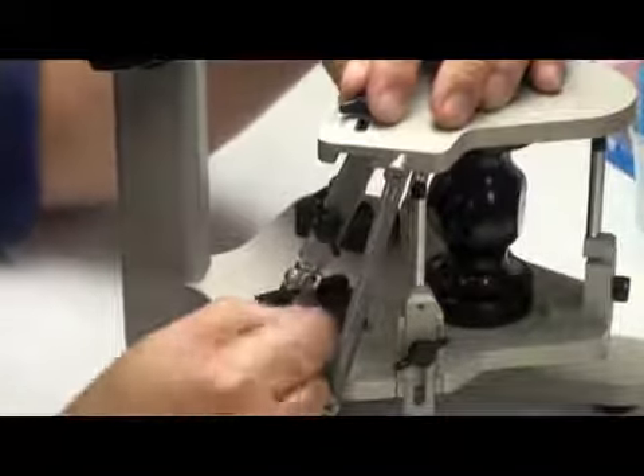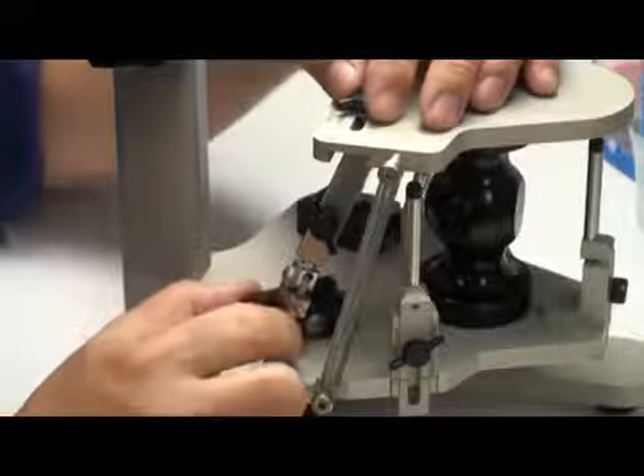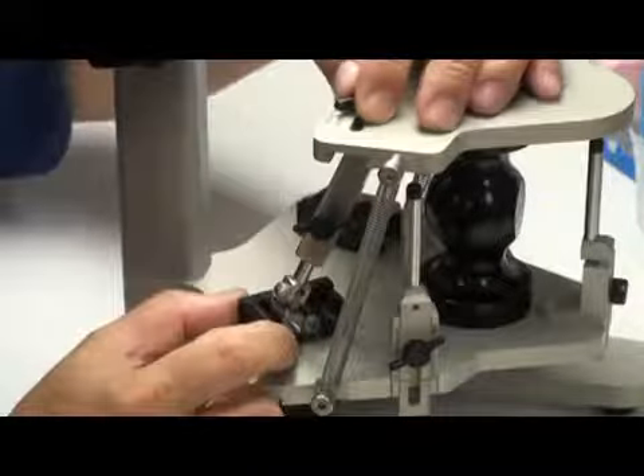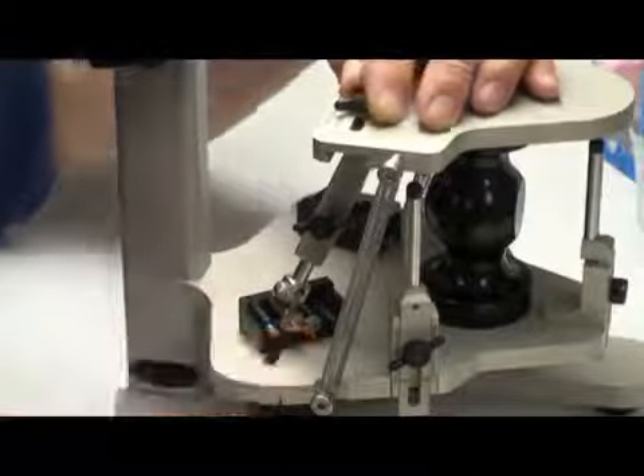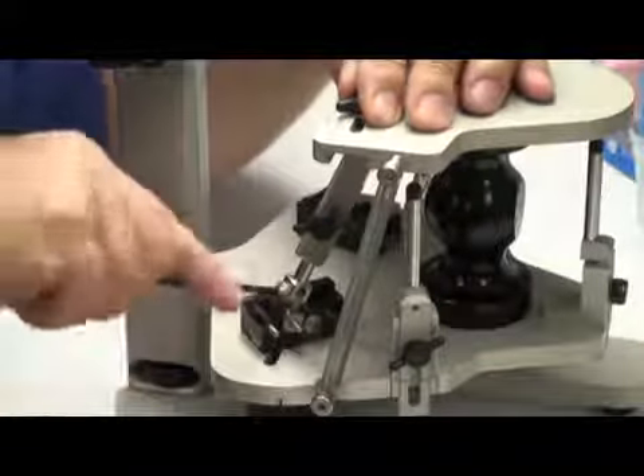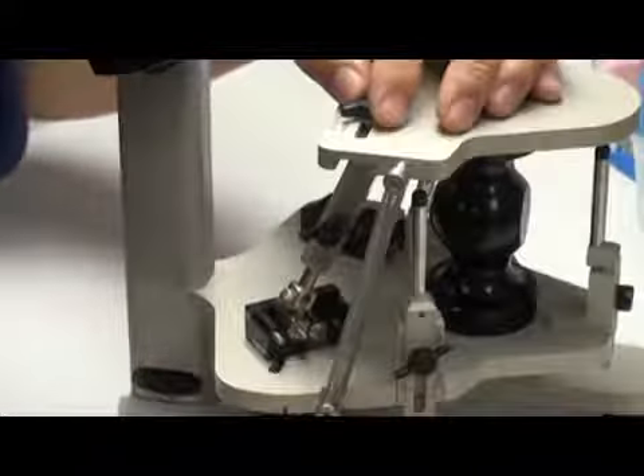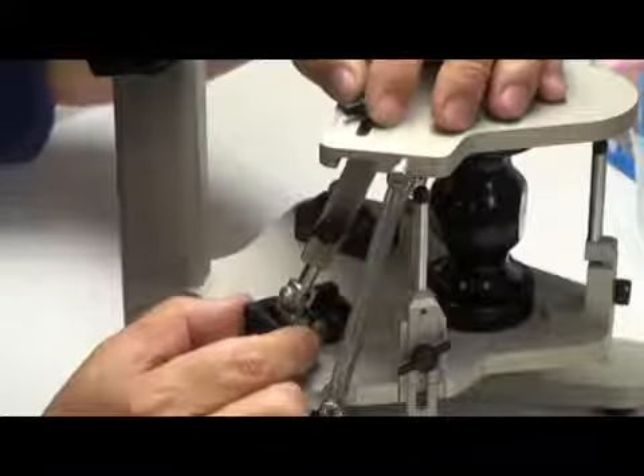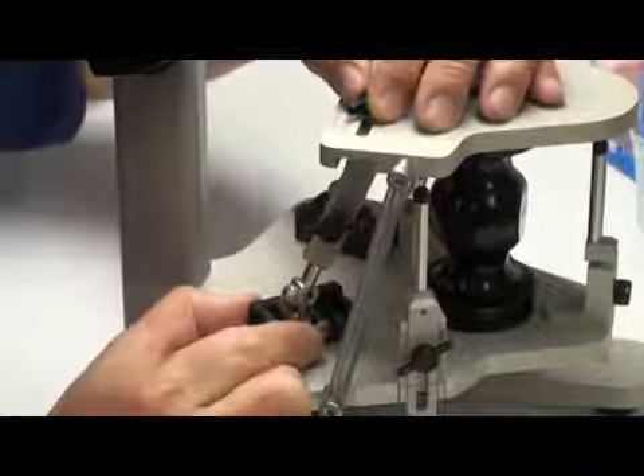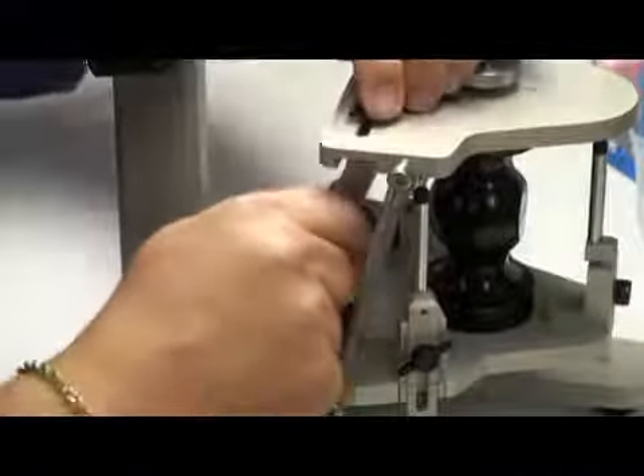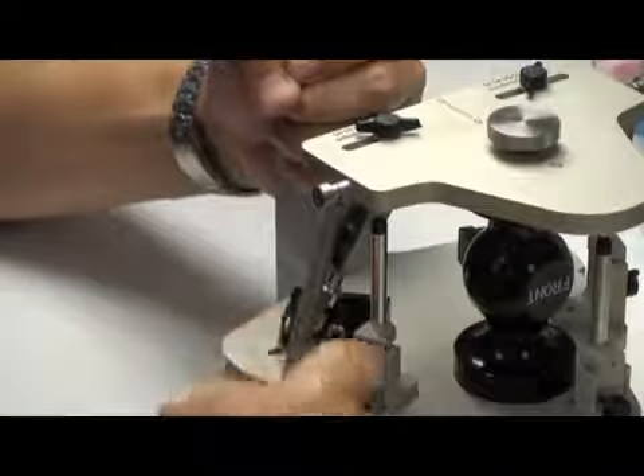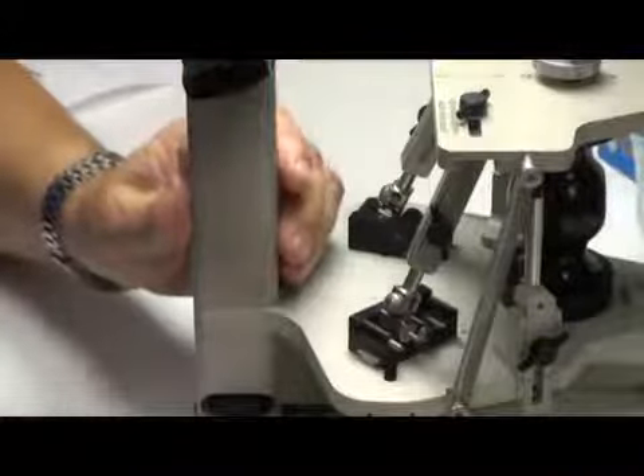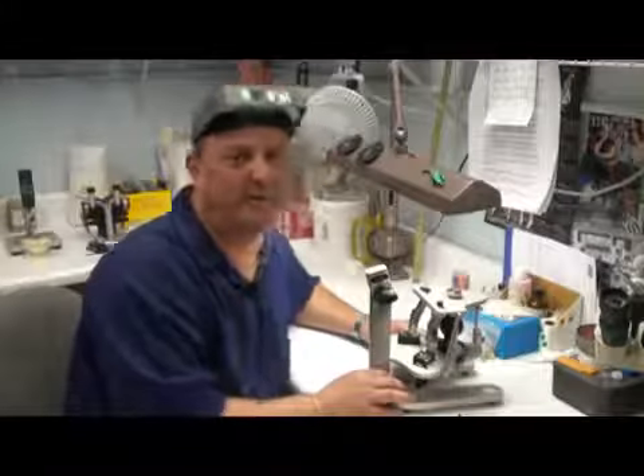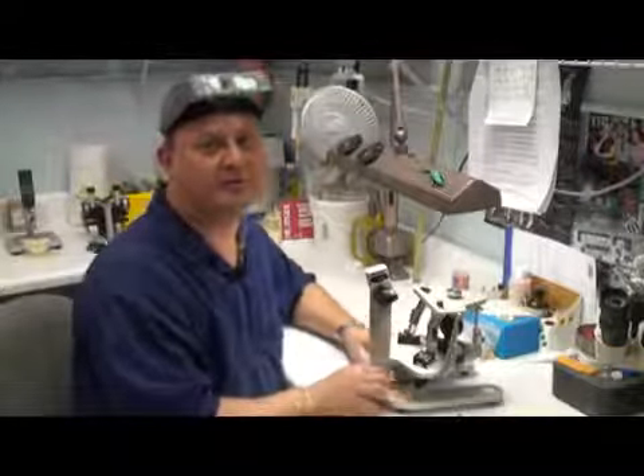At this point, I'm just going to line up the condylar head with the fossa block. Allow it to snap into place, bring it within 1 millimeter. I'll tighten the fossa, or the condylar element, and just tease both pieces into place until they're all tight. The same thing is done on the other side to complete the settings. At this point, all the condylar elements have been set, and we can return the poly to its original position.